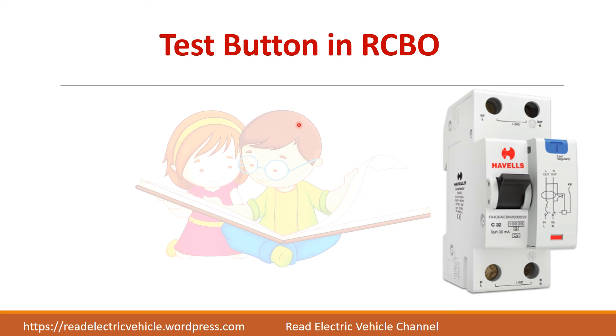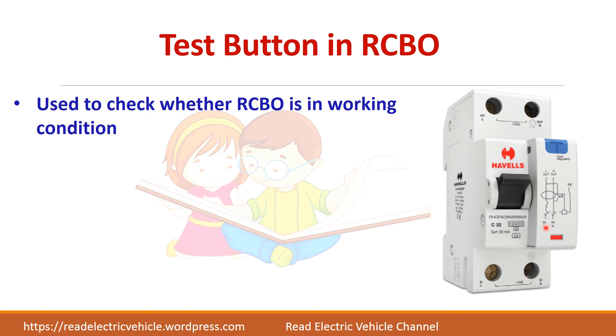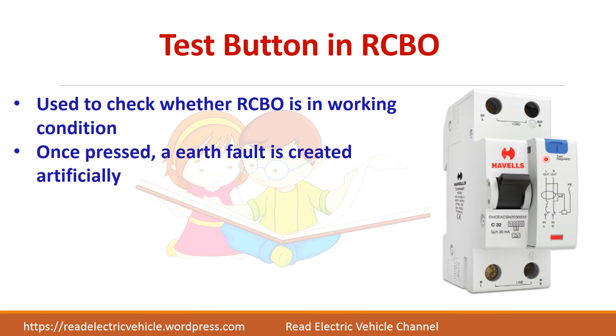Next, we will see about the test button in the RCBO. The test button, marked T, is used to check whether the RCBO is working or not. When you press it, an earth fault is artificially created and the RCBO should trip. If it doesn't trip, it is time to replace the RCBO.